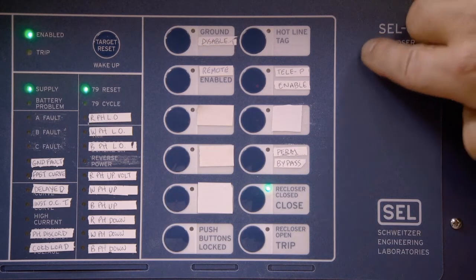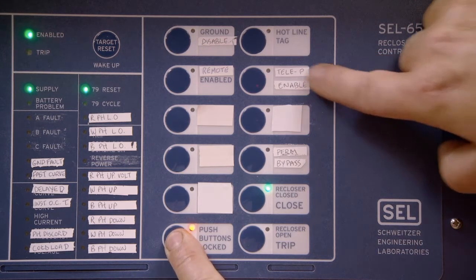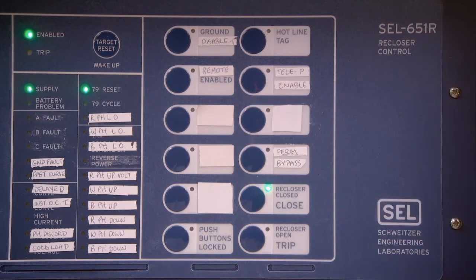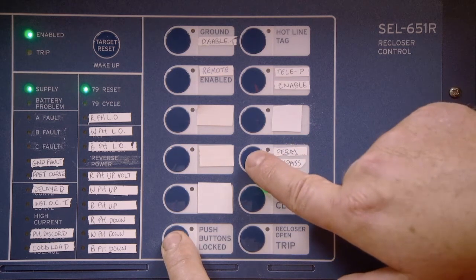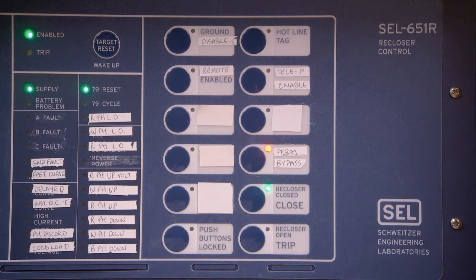Teleprotection enabled. To enable communications for distributed generation or DG operations, press Master Push Buttons Locked and Teleprotection Enabled simultaneously. Permissive bypass. If radio communications fail, the control will be searching for a phantom return signal from the generator. In order for the control to be able to respond to a fault condition, the permissive bypass must be active. When active, the control will enable itself to respond to the fault condition in the absence of the communications link, and permissive bypass simultaneously to allow for full functionality without a generation communication connection.